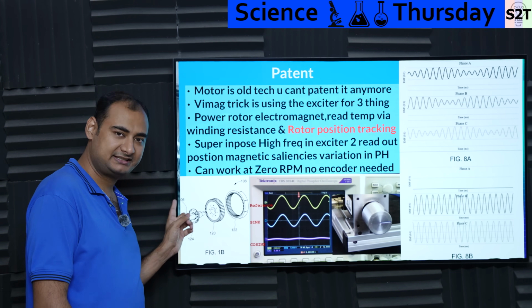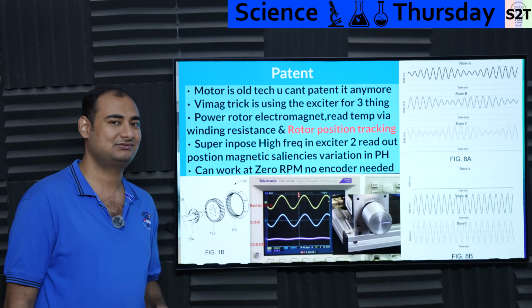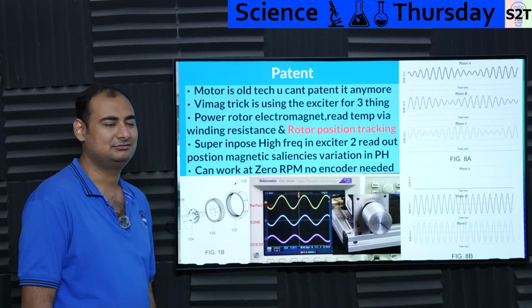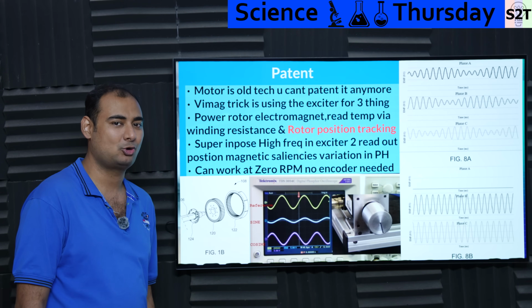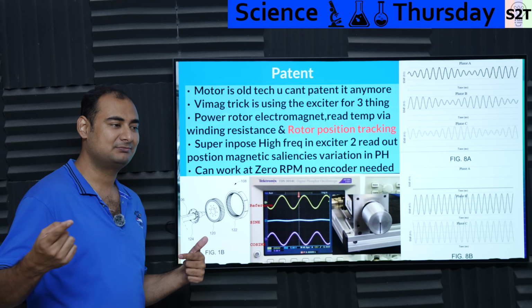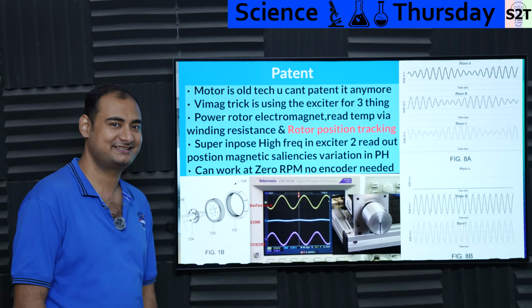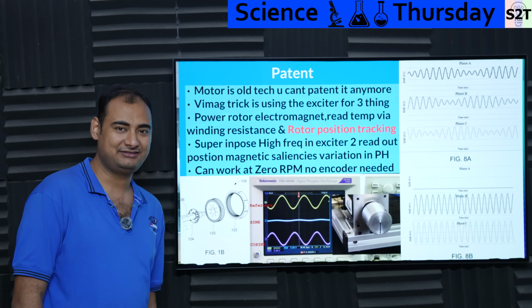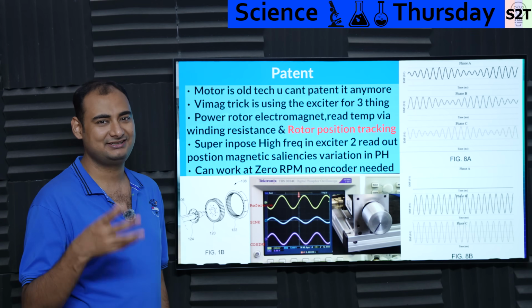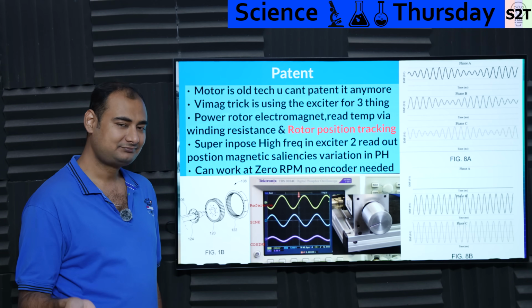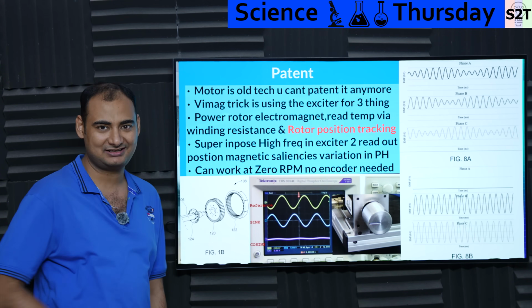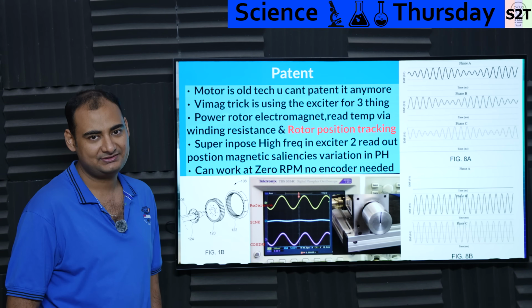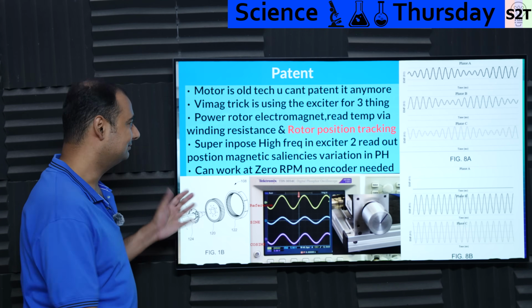They patented using the same pathway to read the temperature of the rotor. How? Well, they're reading the temperature of the coils. Because you have such a long coil path, you can actually detect the resistance, and based on how the current is behaving, you can figure out with good enough accuracy what the resistance of the system is, going through all this wireless hassle. It won't be very precise, but it's better than nothing. Again, it's not very impactful from a utilitarian point of view.